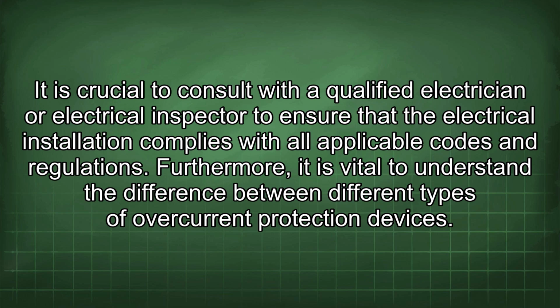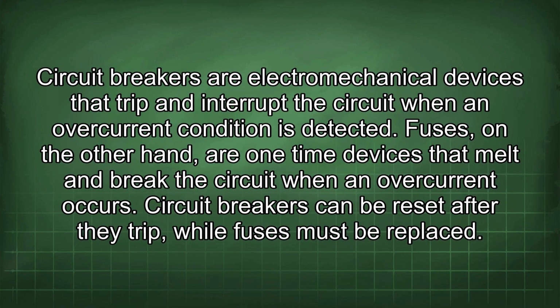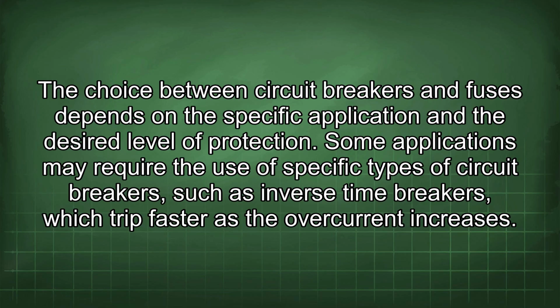Furthermore, it is vital to understand the difference between different types of overcurrent protection devices. Circuit breakers are electromechanical devices that trip and interrupt the circuit when an overcurrent condition is detected. Fuses, on the other hand, are one-time devices that melt and break the circuit when an overcurrent occurs. Circuit breakers can be reset after they trip, while fuses must be replaced. The choice between circuit breakers and fuses depends on the specific application and the desired level of protection.